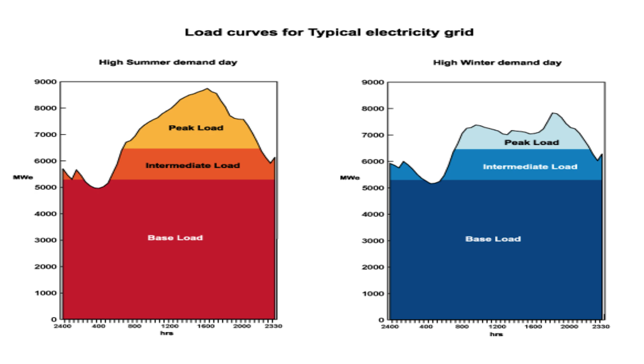So I showed you a demand curve for the shoulder months, which is very tame. Here we are in the summer. So what we have is base loaded units, and I'll go over that in a second. Those are units that run 24/7. That's your big coal plants, your big nuclear plants. They're very slow moving dinosaurs. They move 1 or 2 megawatts a minute.